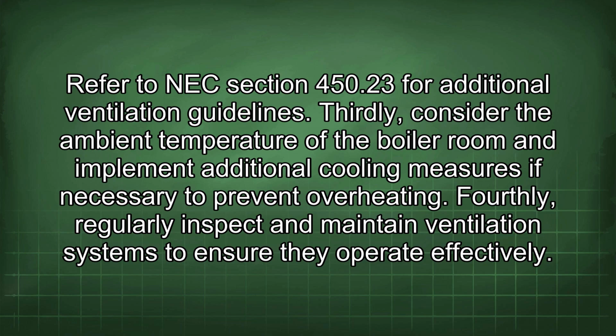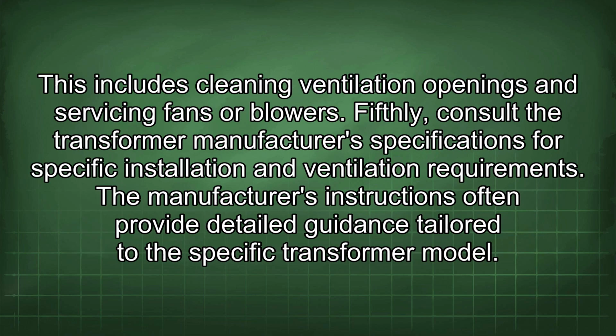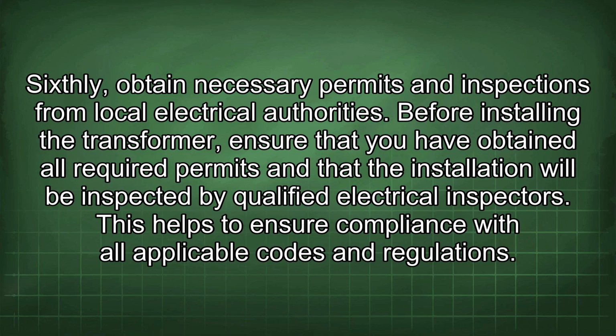Fourthly, regularly inspect and maintain ventilation systems to ensure they operate effectively. This includes cleaning ventilation openings and servicing fans or blowers. Fifthly, consult the transformer manufacturer's specifications for specific installation and ventilation requirements. The manufacturer's instructions often provide detailed guidance tailored to the specific transformer model. Sixthly, obtain necessary permits and inspections from local electrical authorities. Before installing the transformer, ensure that you have obtained all required permits and that the installation will be inspected by qualified electrical inspectors. This helps to ensure compliance with all applicable codes and regulations.